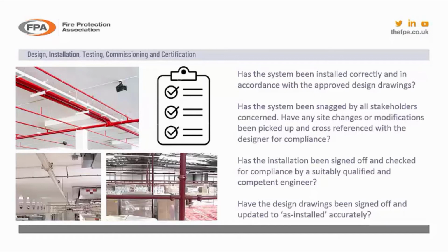It should be checked for confirmation that it meets the requirements of the design drawings, because the design drawings have been approved in accordance with the specification and the standard that they are being designed to. And again, if you're using third-party approved contractors from either of the three certification schemes, they will have engineers that are qualified to sign them off and check them. Once the drawings have been checked and sent back to the office, you've got accurate as-installed drawings. Very important when we're handing the system over later on.